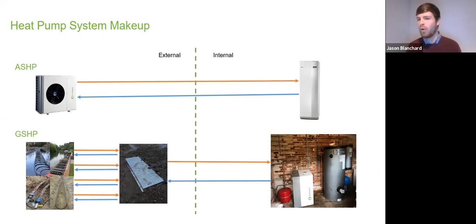For a ground source heat pump, there's a few more options. We'll go into more detail later, but you have your collector, be it from the ground or the water, connections back to a manifold or multiple manifolds depending on the system size, and a single flow and return back to your plant room, which can look a lot prettier than this. You have your heat pump, a couple of tanks, and some expansion vessels. So plant room space is a far bigger consideration with ground source than with air source, which we'll come on to later.